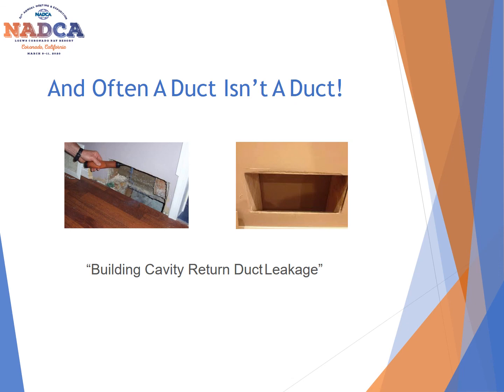And then you have to be aware of situations where it's not even a duct at all. All it is, is a cavity in a wall that's sucking air through, and especially when it's being used as a return duct, what can happen is those return ducts leak dramatically, which pulls in all kinds of excessive dust and debris into your system that you do not want. And if your filters are not working properly, this is where it can become a really major issue, especially when you're dealing with air quality within the facility.